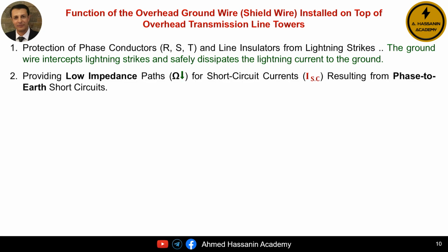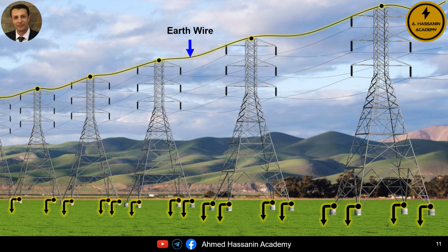The second function is that the earth conductor, shield wire, or ground wire provides low impedance paths, meaning easy paths for earth fault currents. But how does this happen? Of course, we all know that the earth conductor, shield wire, or ground wire is connected to the highest point of the transmission line tower and to the metallic structure of the tower. The second thing is that the earth conductor extends along the entire length of the transmission line, meaning it is connected to all the towers at the top.